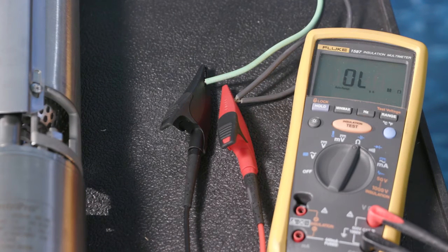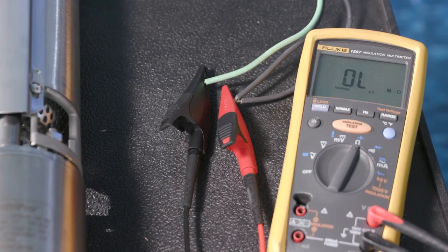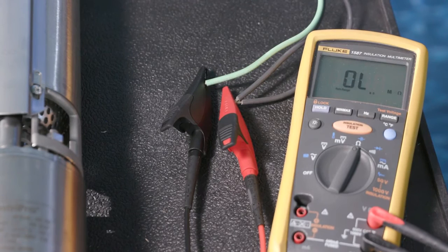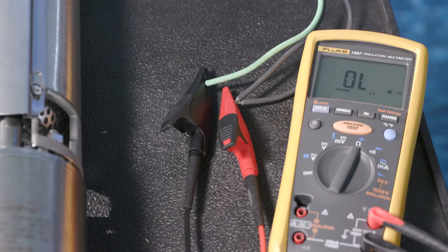To measure line-to-ground resistance with a basic digital ohm meter, first, ensure there is no power to the motor. Measure the resistance between each of the leads to ground. This meter will show OL, or open lead, if the motor has no connection between the power lead and ground. This is a good motor. A bad motor will show a very small resistance value between the power leads and ground.